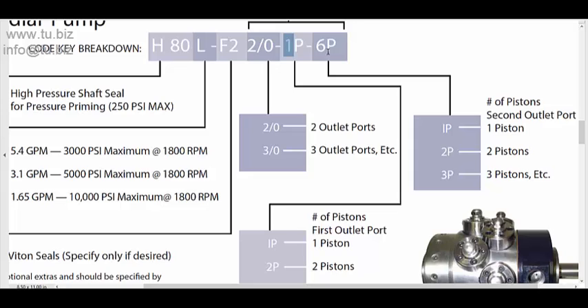Then you go to the next one and you have another five pistons available. It's a total of seven, so you used two, you still have another five. And you can say, okay, for the second position I'm going to put five. This number says six because it's the reference in the catalog, but you can make it five or you can make it four, you can make it whatever amount of pistons that are free that you're not sending to the first port.